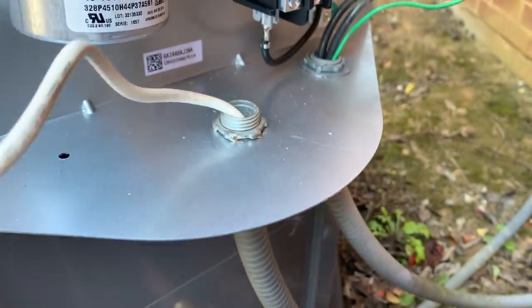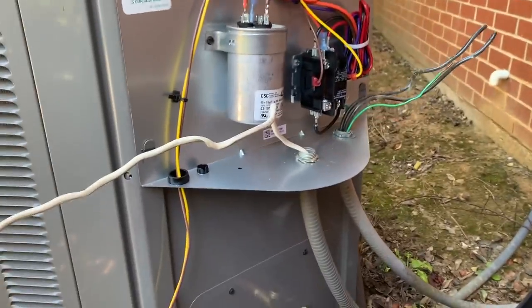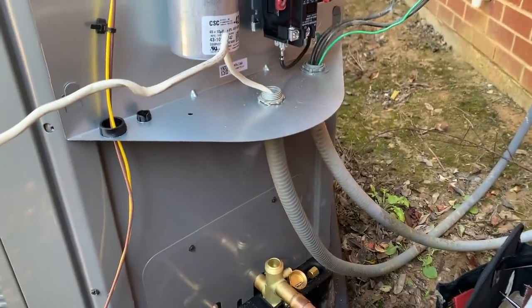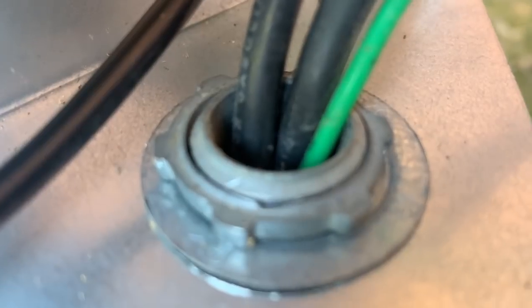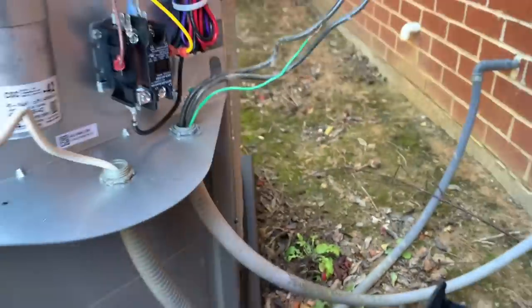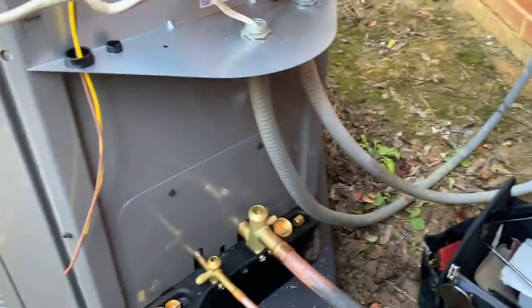Just like I said, this low voltage whip wouldn't reach all the way over here without looking like crap. So I took the unibit and drilled a hole — looks really nice. We have a three-quarter knockout on the unit, and for some reason Rheem does not give you the half-inch pre-knockout option like most units do — they only give you three-quarter. So we carry these reducing rings; that way you can use a half-inch whip if you have one. A reducing ring here and one down below, and that gets the job done.